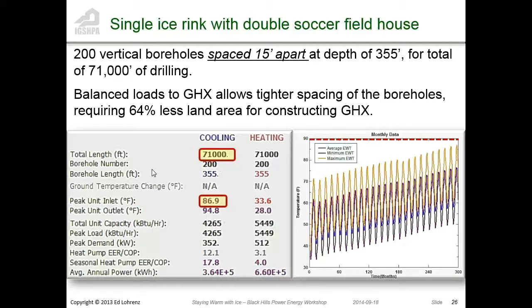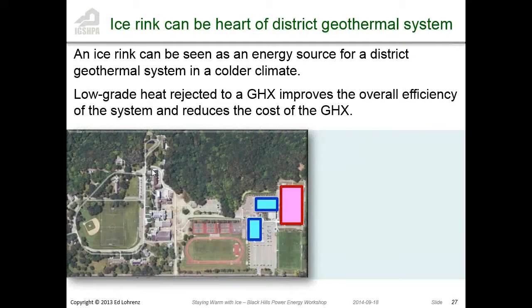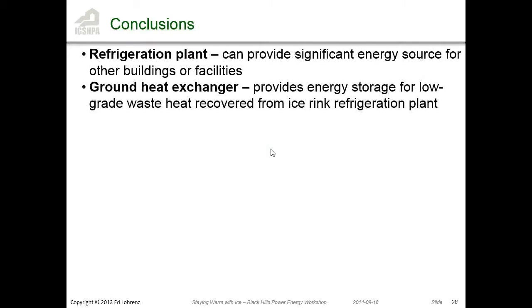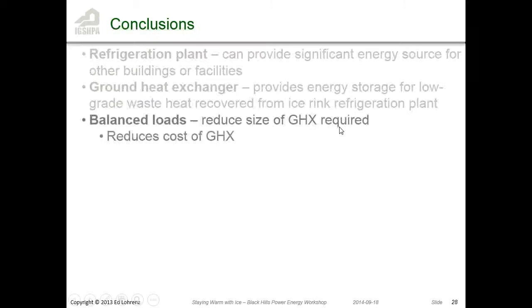So again, you can consider an ice rink as an energy source for a district geothermal system. If you're in a colder climate, it's going to be difficult to use all the heat that you're getting out of an ice rink in Florida. That'd be really, really challenging. You couldn't find enough use for it. So basically, a refrigeration plant and ground heat exchangers provide storage, balancing the loads, and reducing land area.